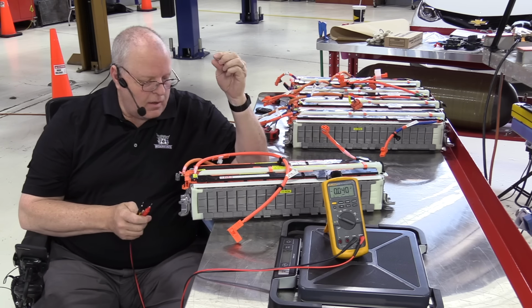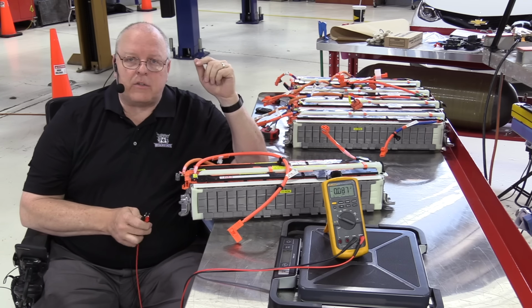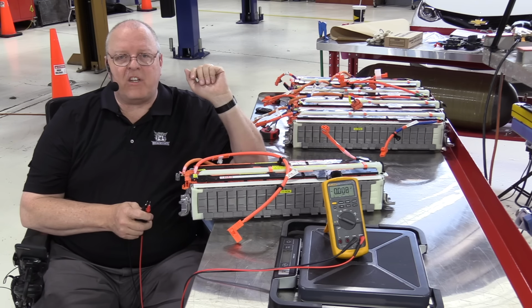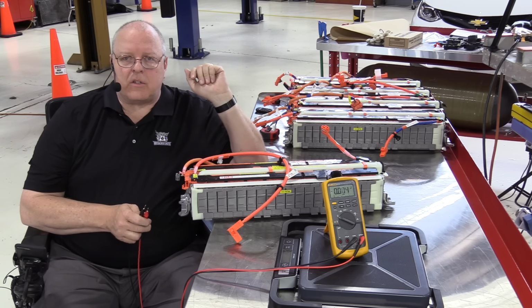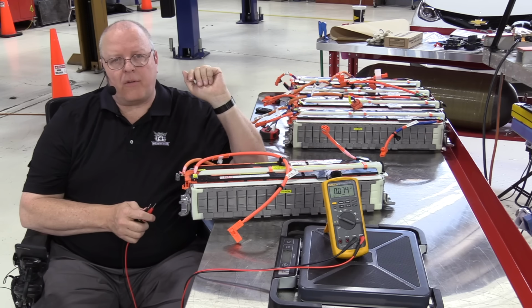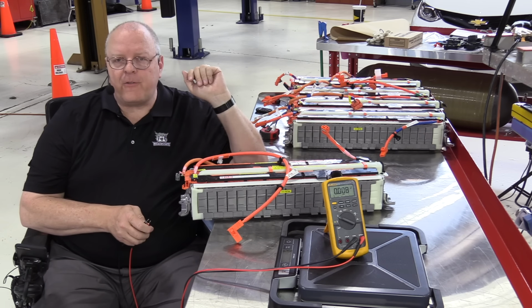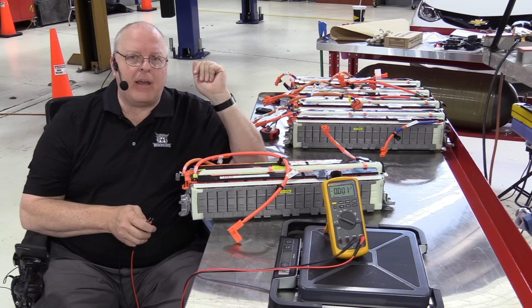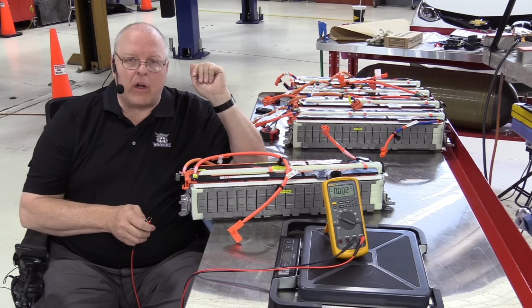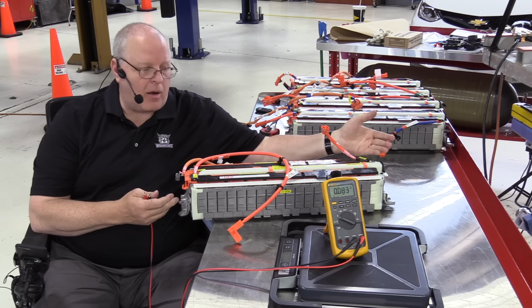It will not. According to OSHA regulations, if you look that up, it refers you to the NFPA document 70E, which tells us we must wear personal protective equipment for anything 50 volts AC and above, and 100 volts DC and above. Well, this is a DC battery.